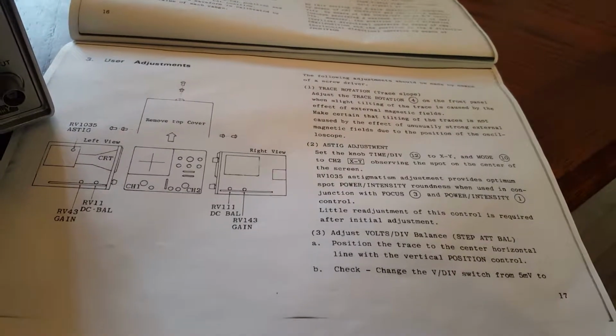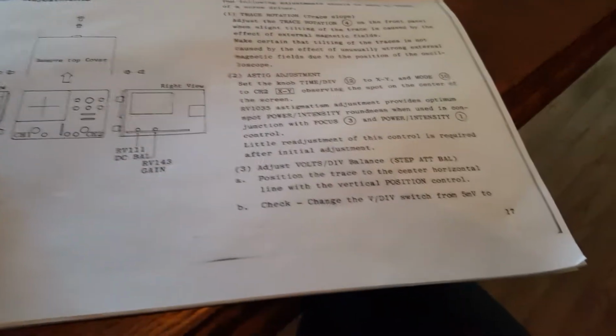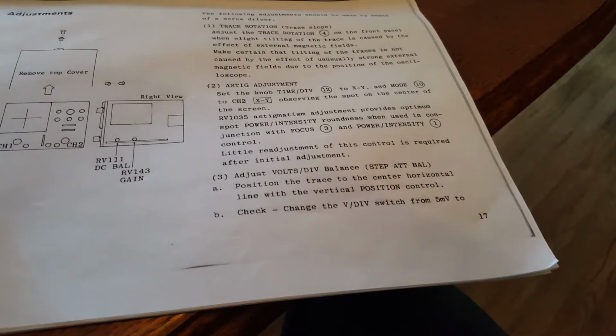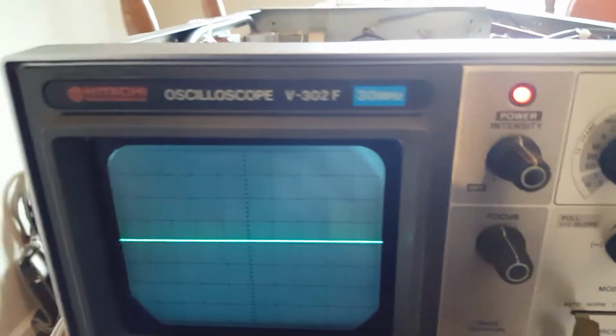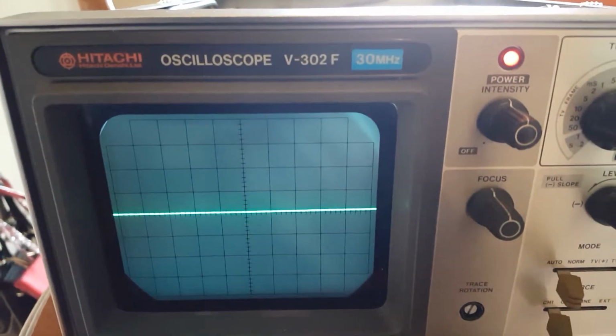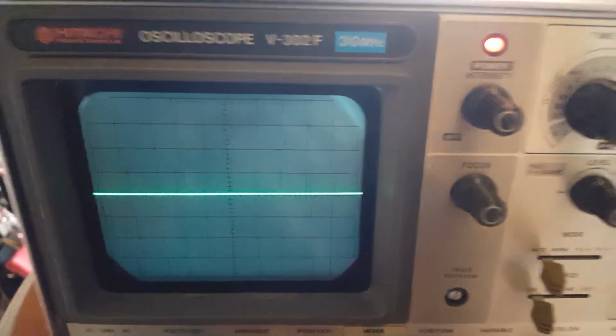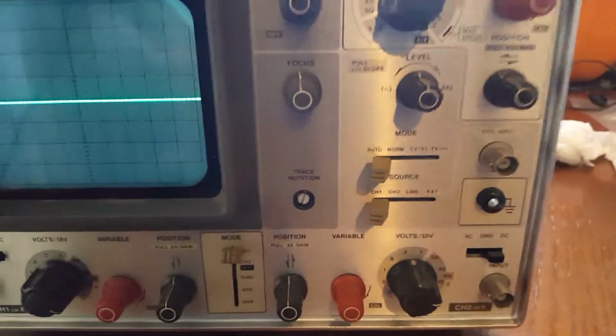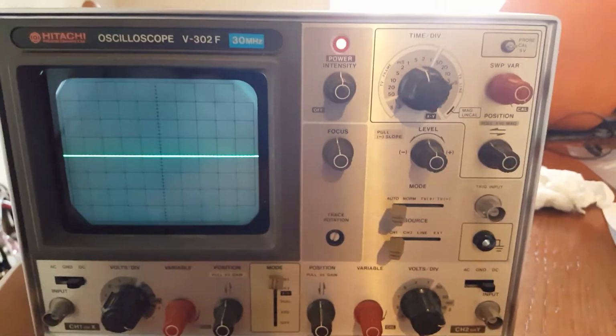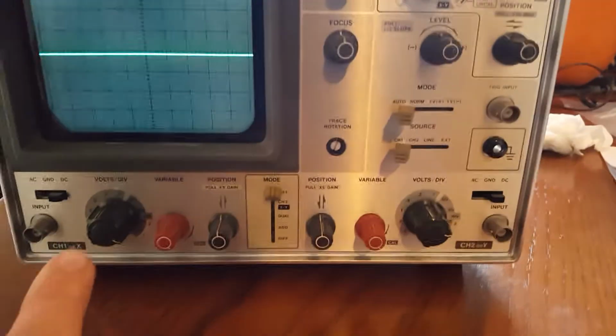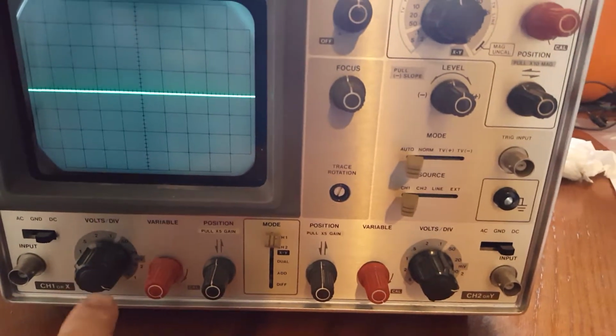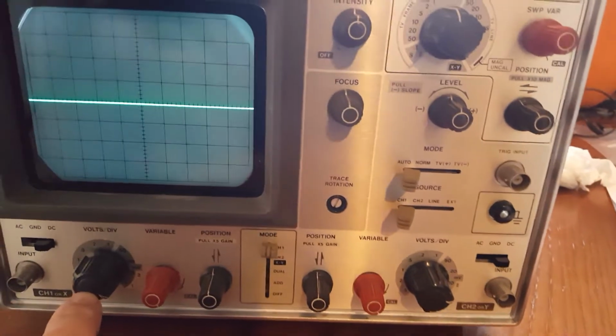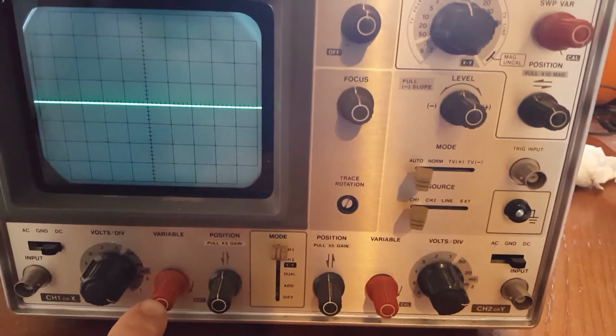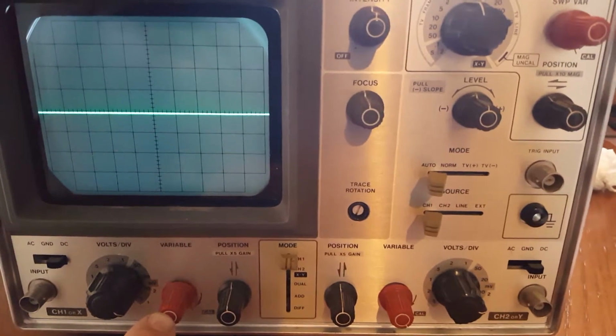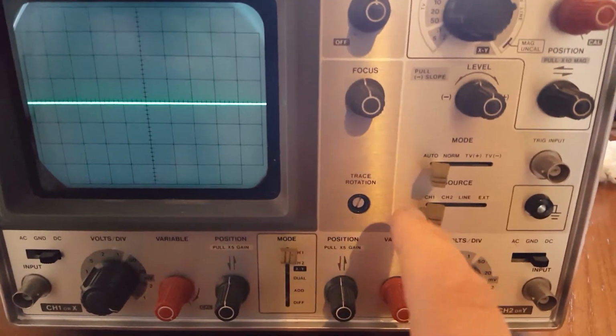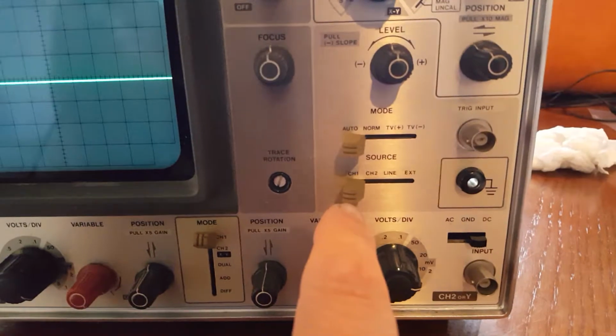This is a short video on how to adjust the volt division balance on my Hitachi Oscilloscope V302F, 30 megahertz bandwidth. To do this, you don't need any probes attached. You want to make sure that your volts per division is on 5 millivolts, that the variable adjustment is all the way down to calibrate, and that mode is channel 1, source is channel 1.